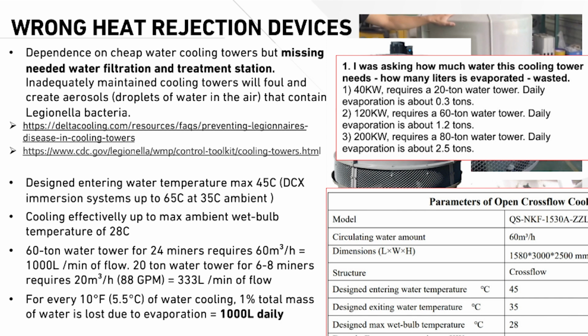People don't think about the amount of water evaporated with a typical cooling tower. For a 1 megawatt system, which isn't that much, you're losing 10 to 12 tons of water every single day. You need to have that water around just to evaporate that much. Such errors, not thinking about the cost of water, have killed at least one company, or almost killed it. This is a pretty important consideration.